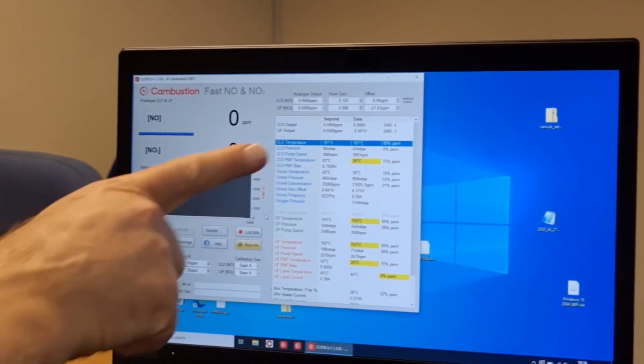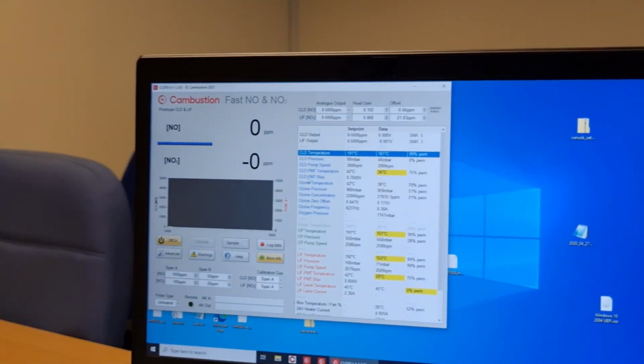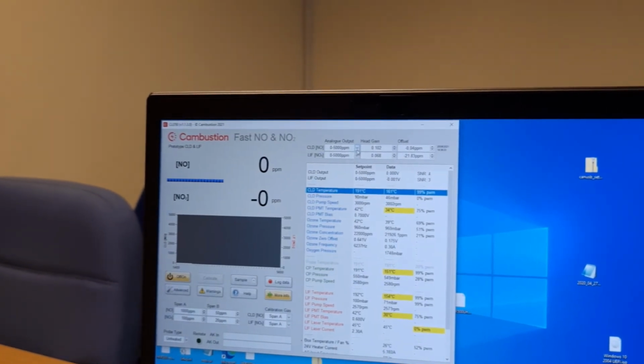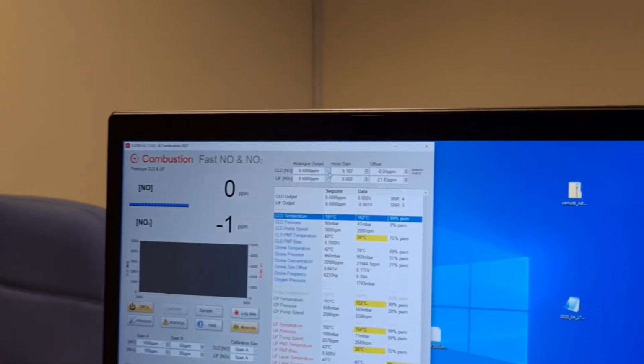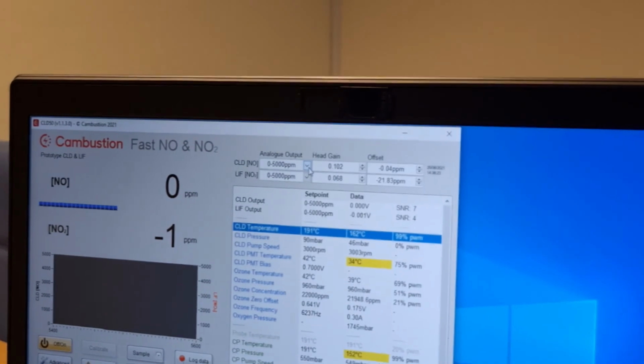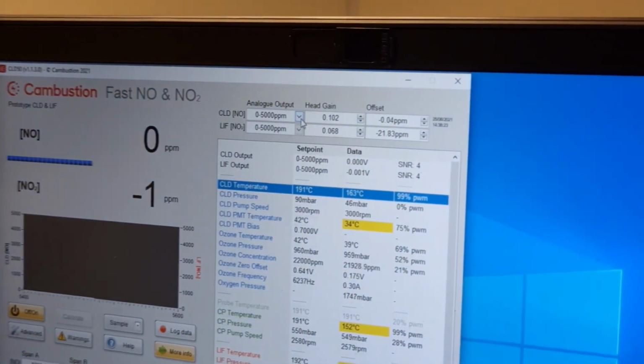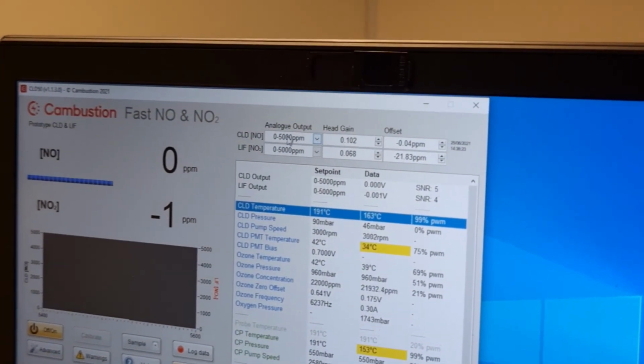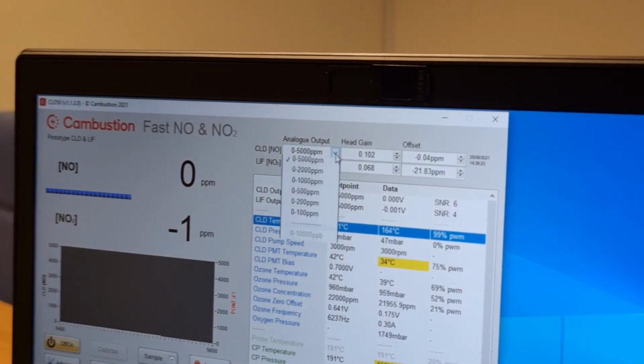The analog output ranges are shown here. So we're currently on a 0 to 5000 ppm output for the NO, which means that the analog outputs on the rear panel, when they're 10 volts, this is equivalent to 5000 parts per million.